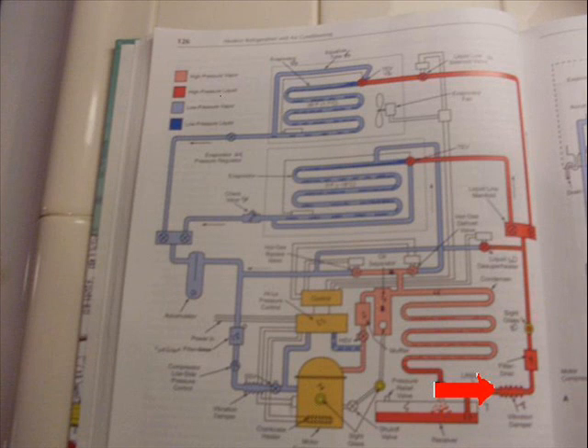Leaving the receiver tank, we may come to a part I'm going to call a vibration dampener. It can go anywhere in the system. It could also be called a vibration eliminator. It is a flexible part that absorbs any vibration and stops the lines from cracking. Vibration will cause cracks in the lines. The vibration eliminator's job is to absorb the vibration and stop refrigerant lines from cracking. And it can be located anywhere in the system.